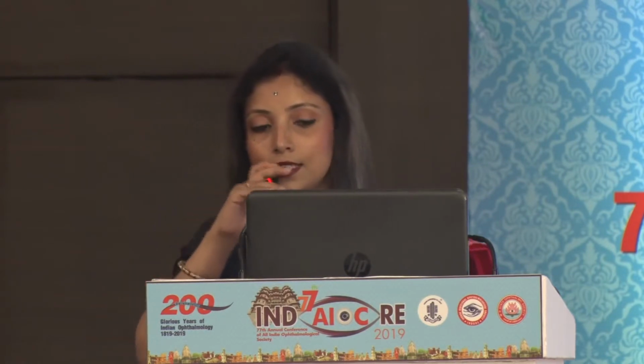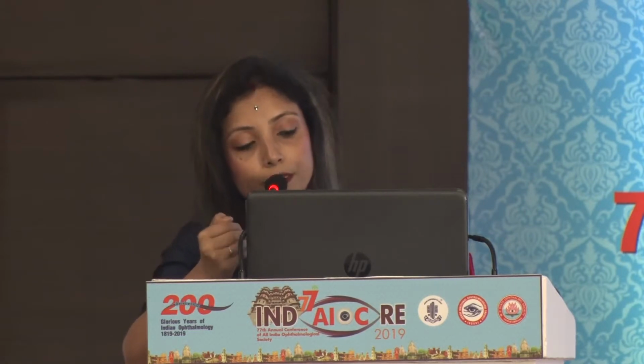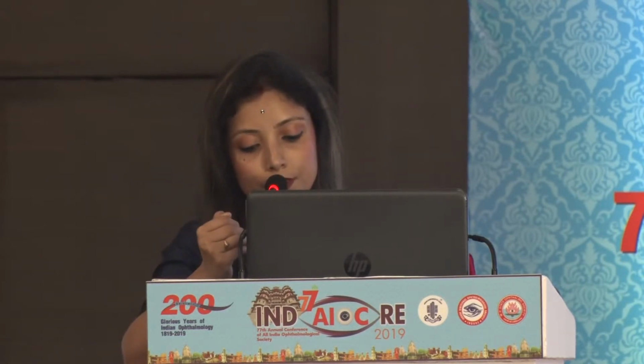The water tank should be a separate one for the OT, and it should be cleaned once in a month, and that cleaning has to be maintained in a register or a logbook. These are the minimum standards that have been put forward by the NABH. The temperature, humidity, air handling, all need to be maintained according to the prescribed guidelines. The occupancy should be limited to 8 persons, and even the equipment load should be limited to 7 kilowatt.